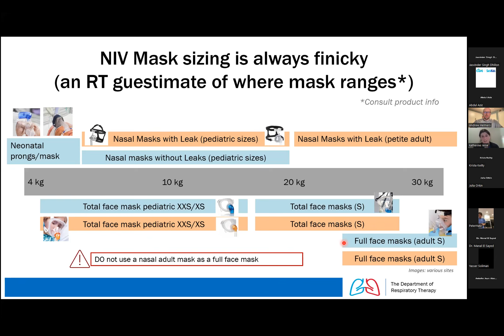So for a 5 kilo patient that we have to use non-invasive, they may only have a tidal volume, or a size of breath, that's about 30 mils. And a lot of these devices have a reasonable amount of leak in them, even if you try your best. So a single limb circuit usually displays a leak in terms of a liter number, whereas the non-invasive dual limbs usually display the leak as a percentage. And so a lot of people will see a leak on the dual limb that's 80 to 90%, and that makes them concerned because it looks like a really large leak, and they may try to address that.